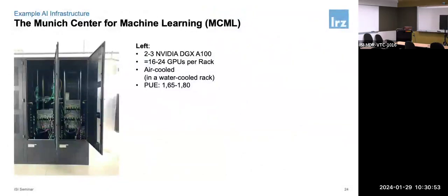Here you see our system, which is interesting because we're doing a water cooled rack. There's a heat exchanger with cold water, and we have the same blocks up here. You see 3 here and 2 here, meaning we cannot fit more than 3, because the cooling capacity of our racks today just does not allow it. Each of them has about 8 kilowatts, giving about 24 kilowatts cooling capacity per rack. That's the maximum.